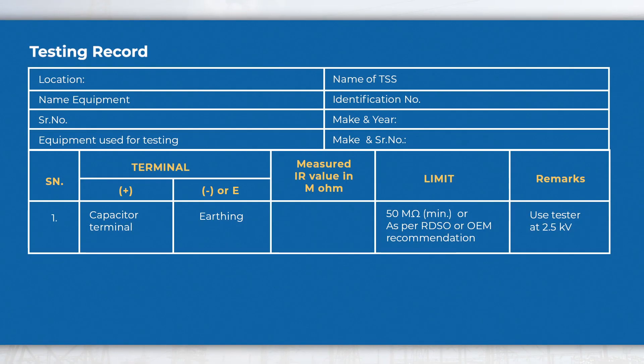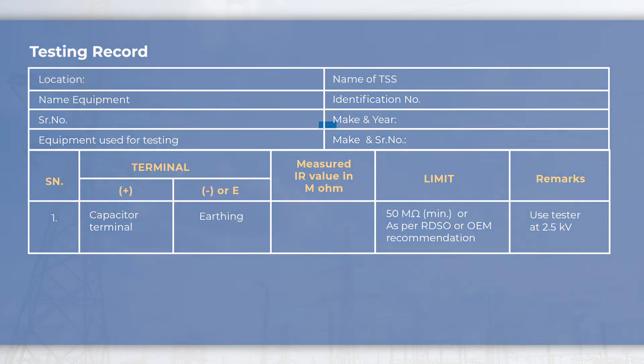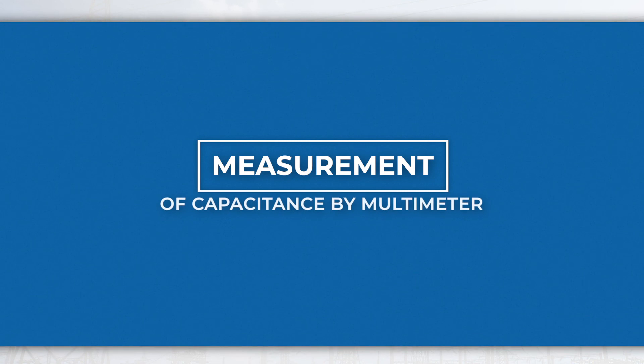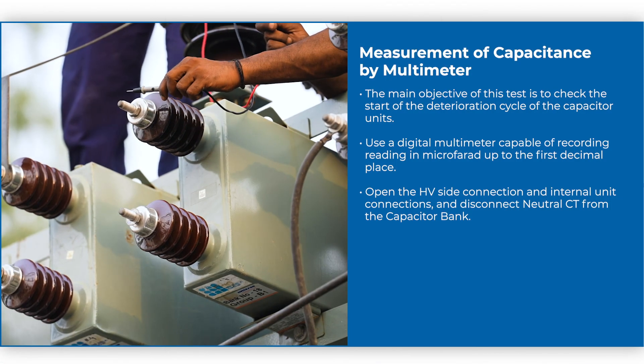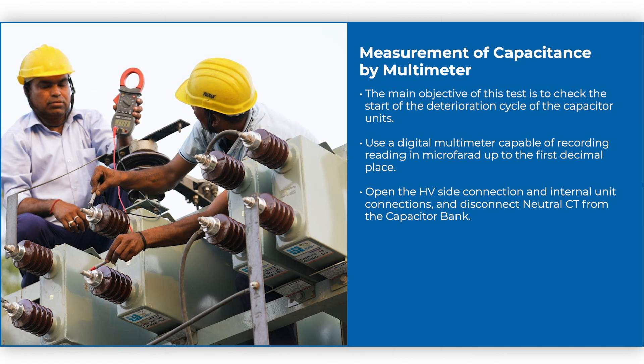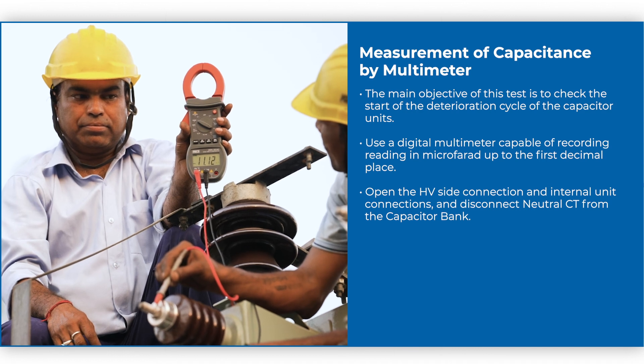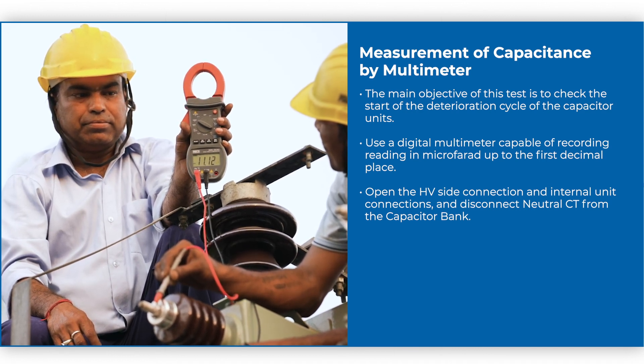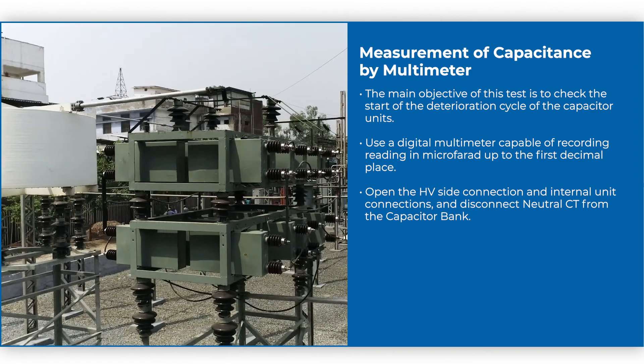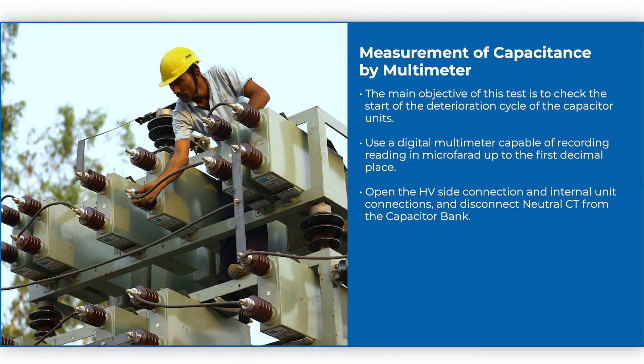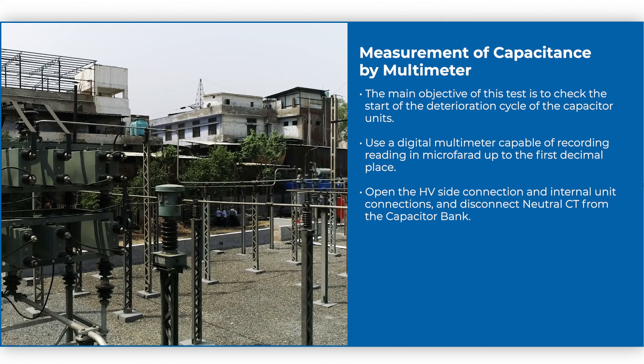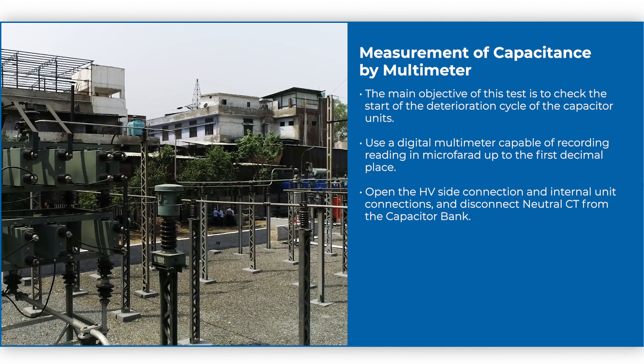Testing data may be recorded in the specified format for further investigation and future reference. Measurement of capacitance by multimeter: the main objective of this test is to check the start of the deterioration cycle of capacitor units. Use a digital multimeter capable of recording readings in microfarads up to the first decimal place. Open the HV side connections and internal unit connections and disconnect the neutral CT from the capacitor bank.